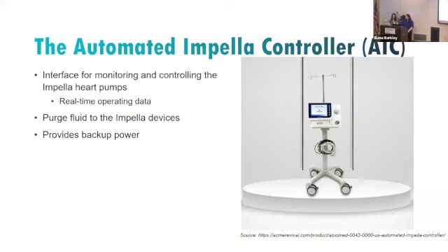All right, another part of the Impella device is the automated Impella controller. This is what your Impella catheter is attached to by the cable. It provides insight into the catheter function at a glance. It's an interface for monitoring and controlling the Impella heart pumps. It provides real-time operating data. It also delivers purge fluid to the Impella devices. The purge fluid is used to prevent clotting in the cannula, and it also provides backup power. So when it's fully charged, it can operate on its battery for at least 60 minutes.